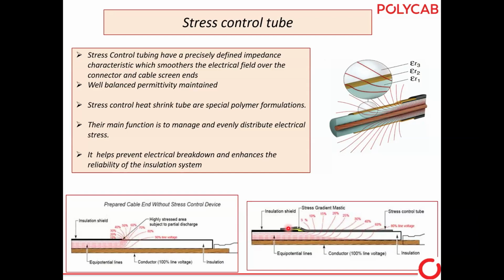Now let's see what happens if we use the stress control tube. This is a stress control tube we have installed on the cable, and the yellow part is the stress grading mastic. Now see, when you charge the cable, how the equipotential lines are deflected. It is not concentrating at this point. So stress is not developed at this point, and failure will not happen at this point. That's why the stress control tube is very important for any cable accessories manufacturer, from medium voltage to extra high voltage also.